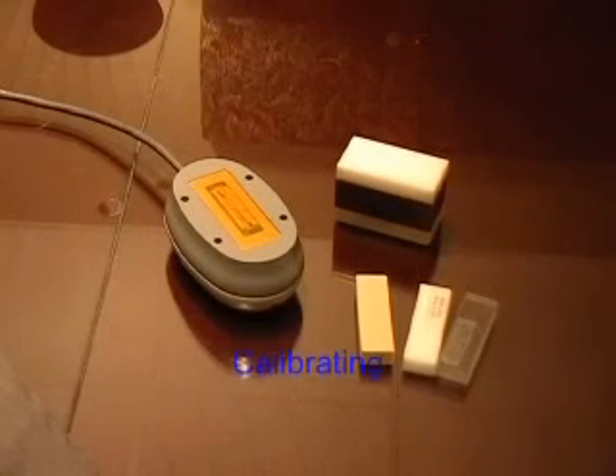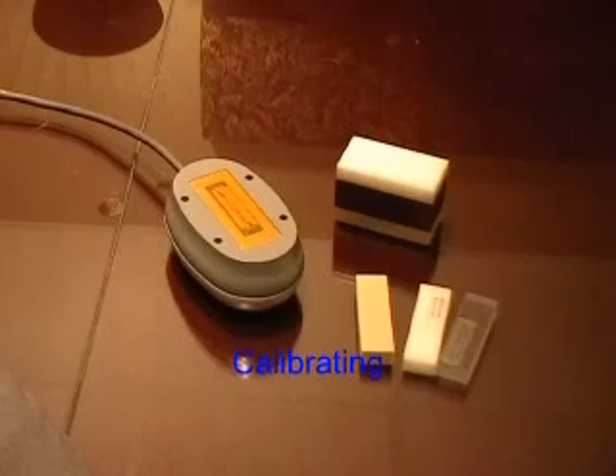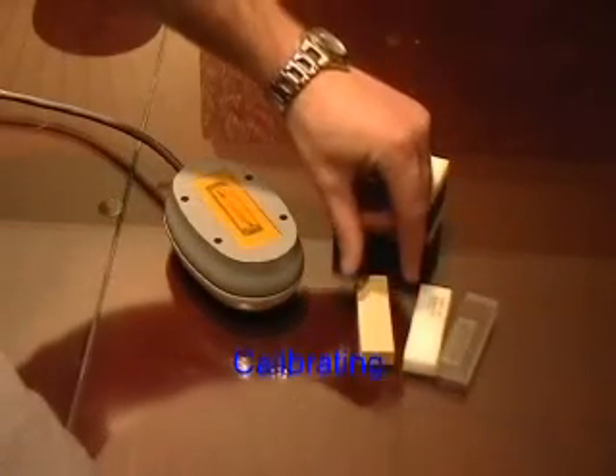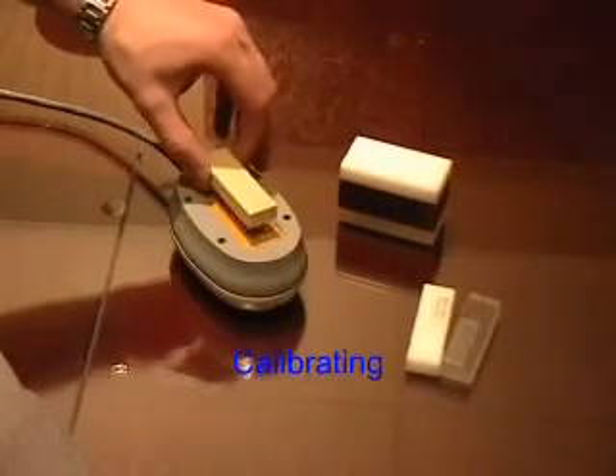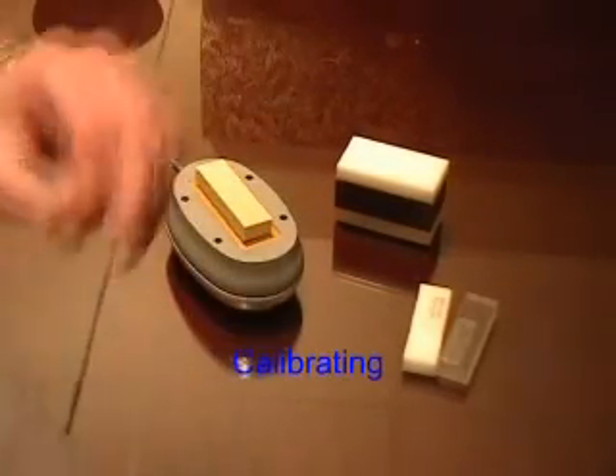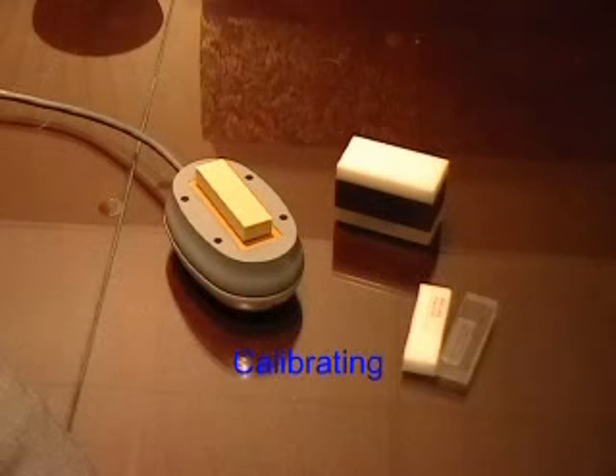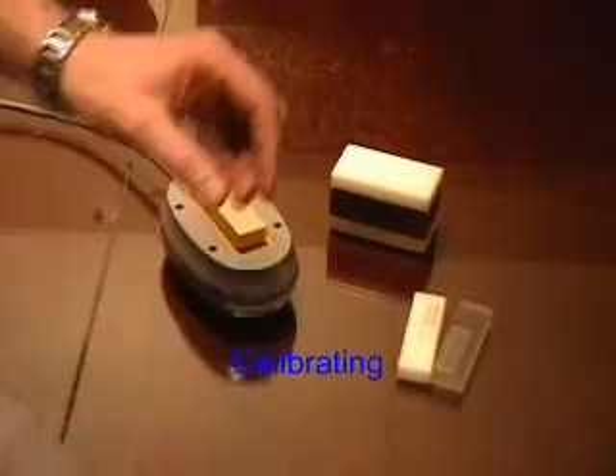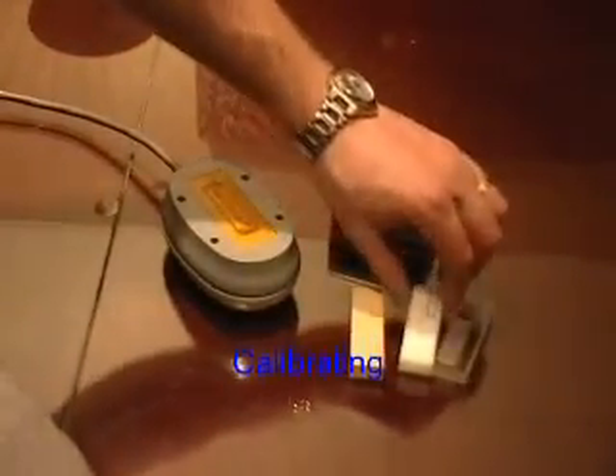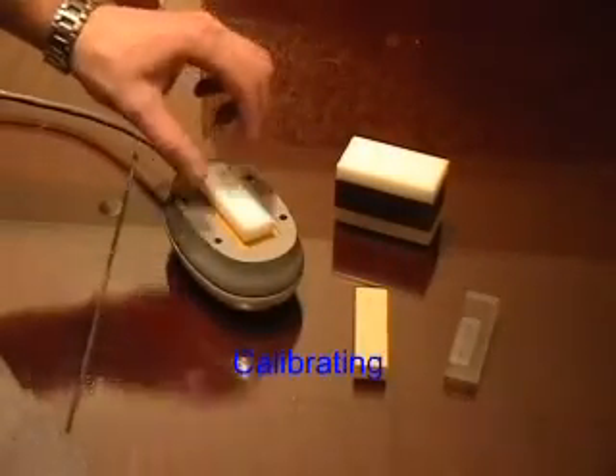Now that we've determined 1 second to be the appropriate test time for our 5 layers of paper, let's calibrate the TC-30. The first step in calibration is choosing 3 appropriate standards from our basic calibration kit. In this case, I've chosen Elastofoam, HDPE, and Pyrex. Then, by placing each standard on top of the sensor and testing for a period of 1 second, which we determine with the Blotter Technique, we will have an instrument response against this thermal conductivity standard. Repeat this for each standard to get an instrument response for different conductivities.